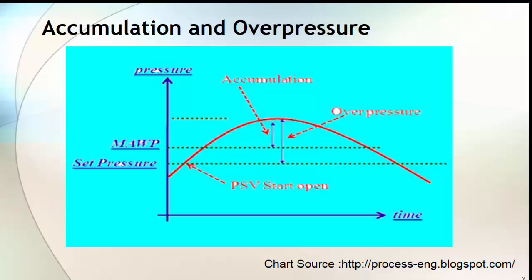Accumulation is the pressure above the Maximum Allowable Working Pressure that the vessel experiences during a high pressure event. Hence when we say accumulation, we are talking about the vessel or the equipment. On the other hand, overpressure is the pressure above the set pressure of the Pressure Safety Valve that the PSV experiences during a high pressure event. Hence when we say overpressure, we are talking about the Pressure Safety Valve.